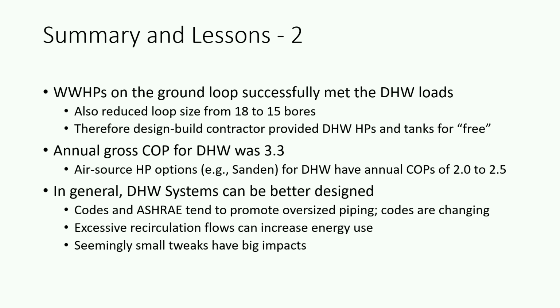So the water-to-water heat pumps worked pretty well to meet the domestic hot water heating load. Jens was able to downsize the loop from 18 bores to 15 bores. He always likes to say he provided the DHW system for free because the reduction in loop size offset the cost of the DHW system. The annual gross COP for the domestic hot water system was 3.3, and any air source system would have been more like 2 to 2.5 for comparison.